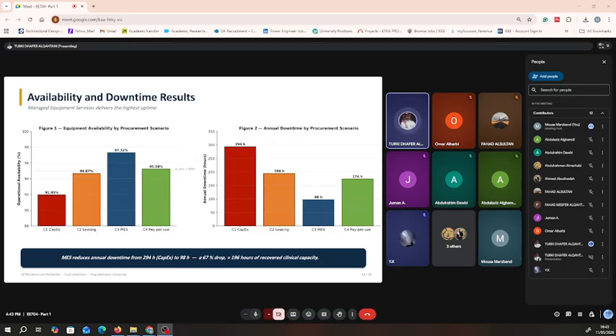This slide presents the operational side of the results. Managed equipment services achieve the highest availability, around 97.3%, while CAPEX is around 92%. In terms of downtime, on the right of the slide, CAPEX gives about 294 hours per year, while managed equipment services gives about 98 hours per year. That means moving from CAPEX to MES reduces annual downtime by about 67%. Operationally, this is very important because it means more usable clinic time, better service continuity, and patient satisfaction.